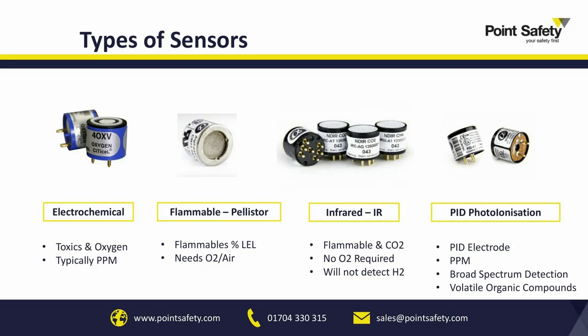We would then have infrared or IR sensors. IR sensors are used again for flammable gases, but also CO2. 99% of all CO2 sensors will be infrared, and they also don't require O2, oxygen, in order to function. So in inert atmospheres or blanketing at the top of tanks, they will still pick up the flammable gases without the requirement of oxygen to be in the sample.